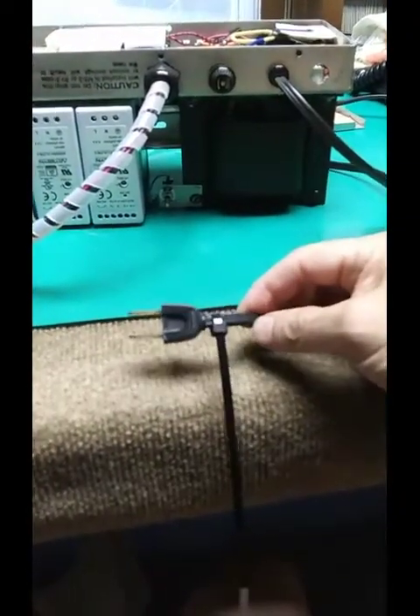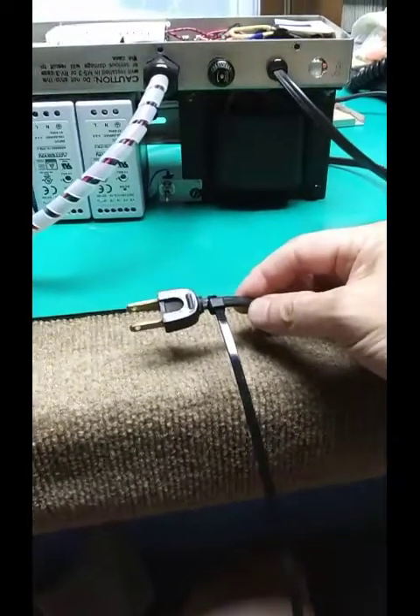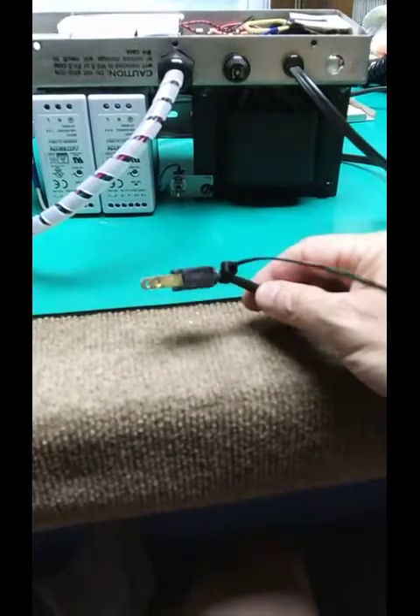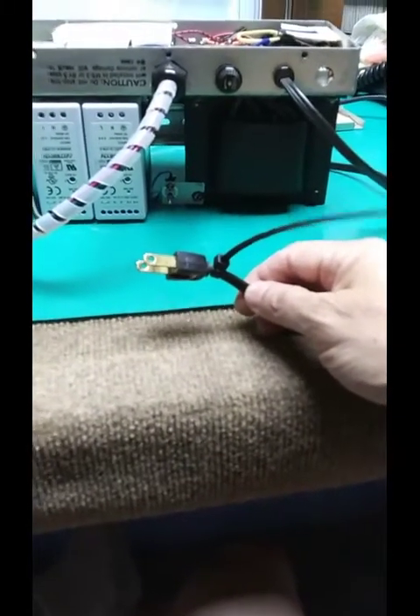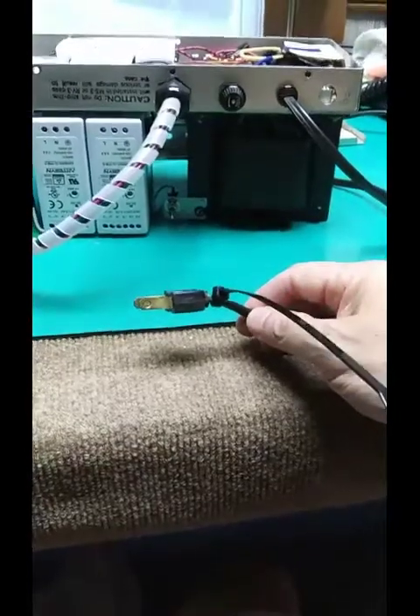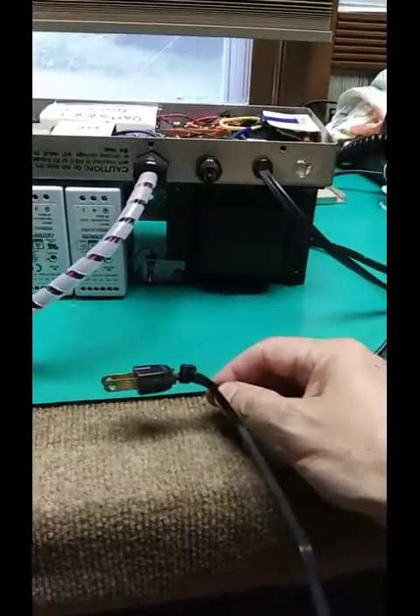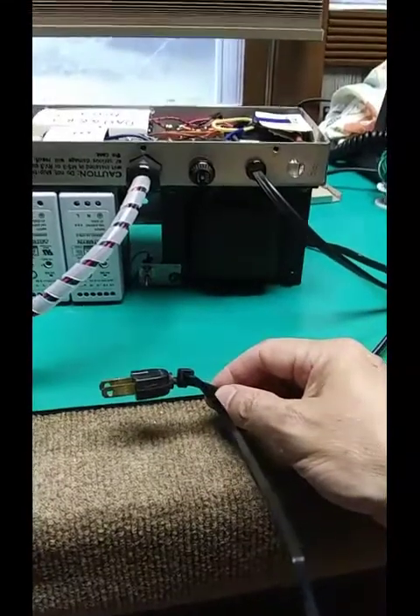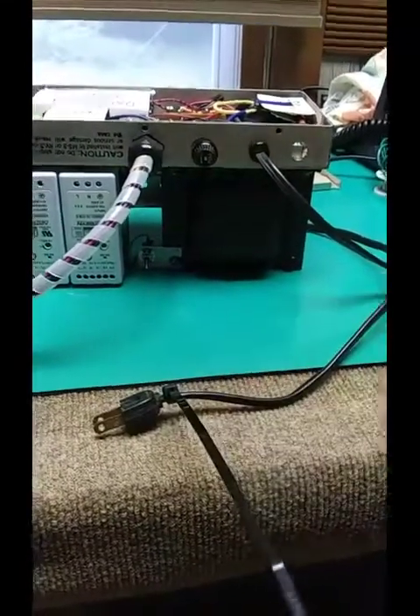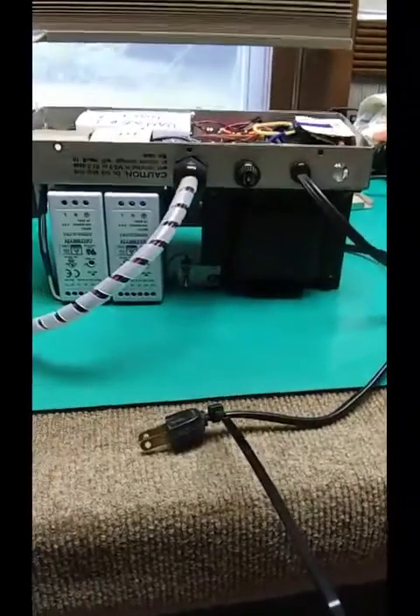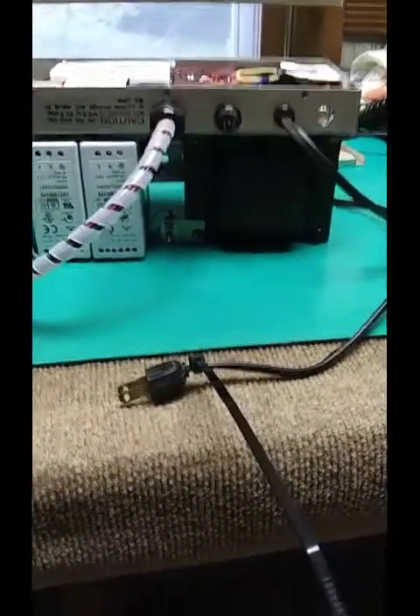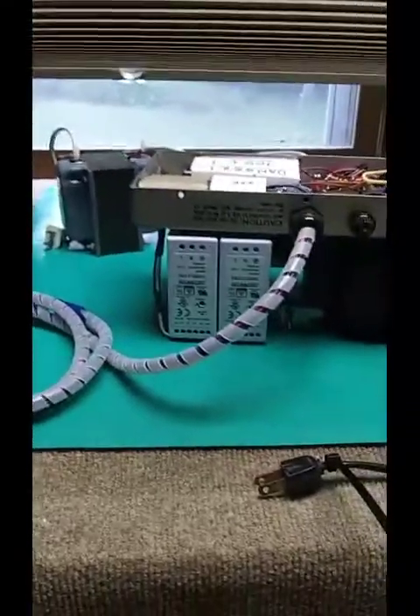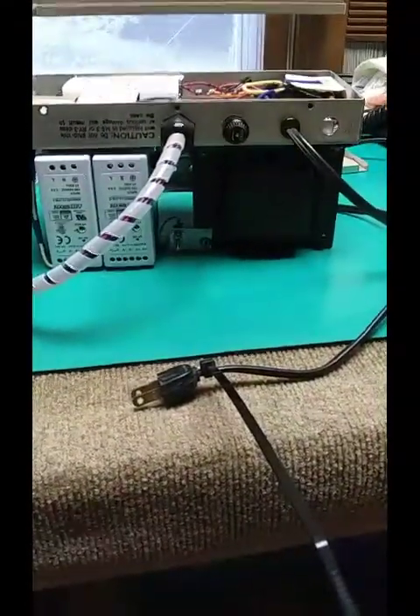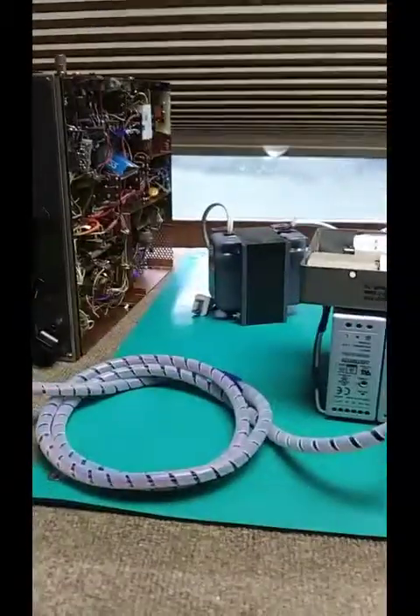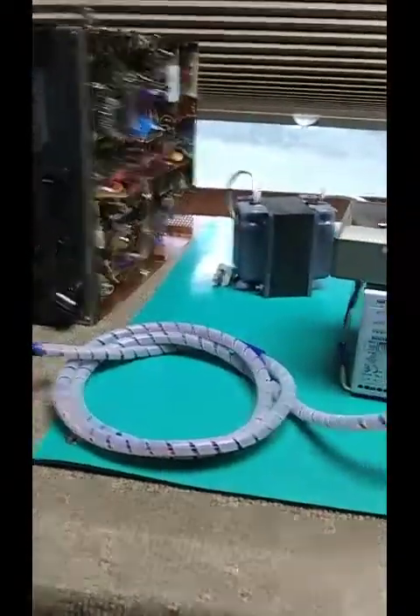If you'll see the zip tie, the head of that zip tie is on the side that must be connected to L1 or hot on the AC outlet, which is the narrow blade, in order to minimize AC leakage across that transformer, which indicates it's not an isolation transformer because it has a fair amount of leakage. But to minimize AC leakage between the line through that transformer to the chassis to some other piece of equipment. And there was a noticeable AC voltage difference between this chassis and I think it was the ASU. I reversed the plug. Most of it went away.